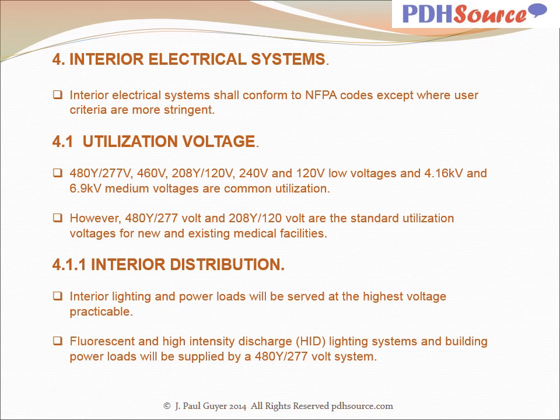Now some comments on interior electrical distribution systems. Interior electrical systems shall conform to NFPA codes except where user criteria are more stringent. Utilization voltages 480Y/277, 460, 208Y/120, 240 and 120 low voltages, and 4.16 kV and 6.9 kV medium voltages are common utilization voltages. However, 480Y/277 and 208Y/120 are the standard utilization voltages for new and existing medical facilities.